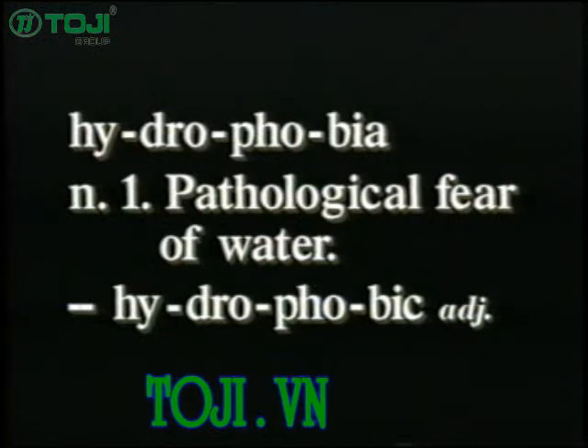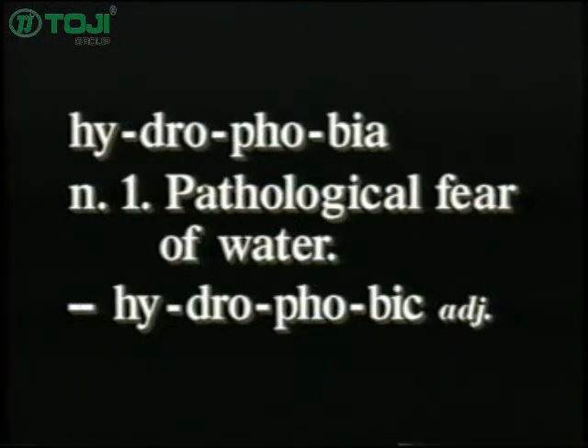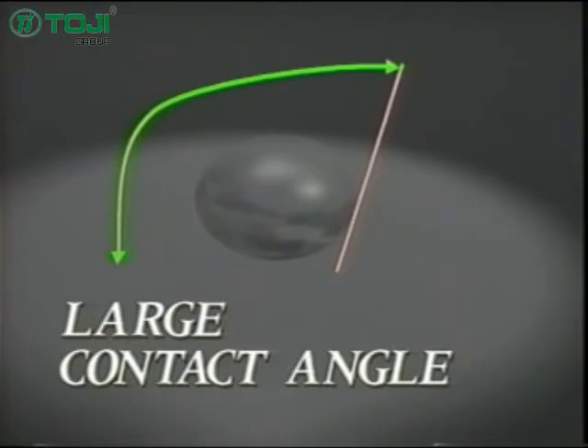Hydrophobicity, or water resistance, is a very key feature required for designing terminations that will last the life of your cable. Silicone is the only material of the four that is truly hydrophobic. Hydrophobic surfaces cause water to bead up, causing the moisture to take up the least amount of surface coverage, forming a large contact angle between water beads and the insulator surface. A large contact angle results in the least amount of surface wetting.